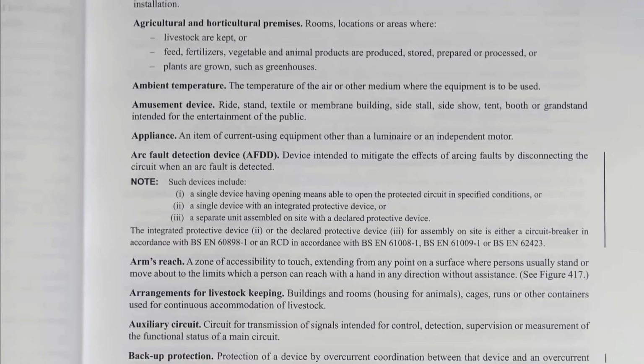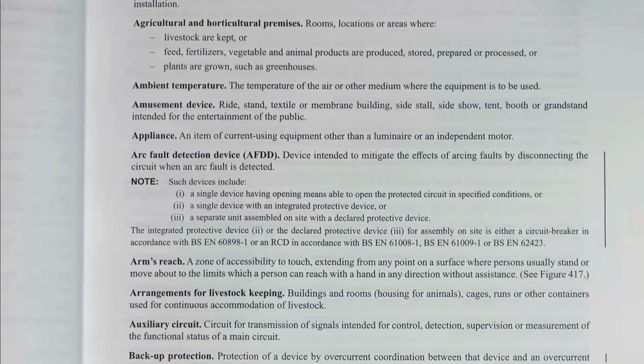The first addition here is arc fault detection device. Despite these being included in previous versions, this is the first time it's actually been defined. An arc fault detection device, or AFDD, is a device intended to mitigate the effects of arcing faults by disconnecting the circuit when an arc fault is detected. Such devices include a single device having opening means able to open the protected circuit in specified conditions, a single device with an integrated protective device, or a separate unit assembled on site with a declared protective device, and there are certain standards they need to comply with.